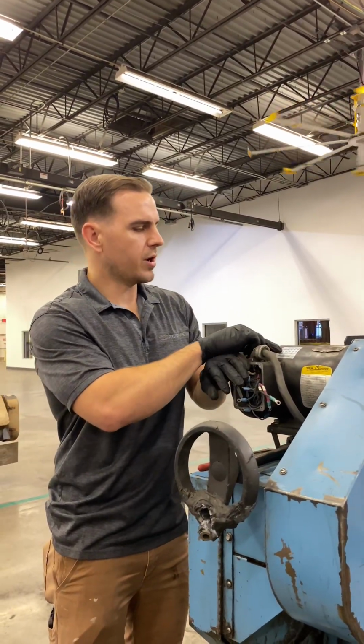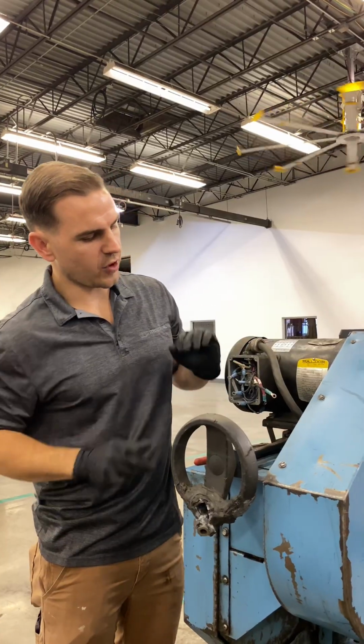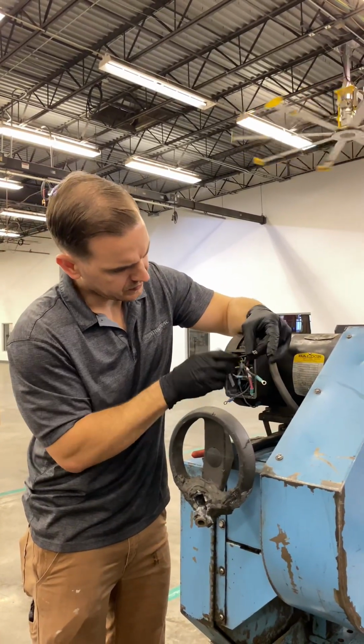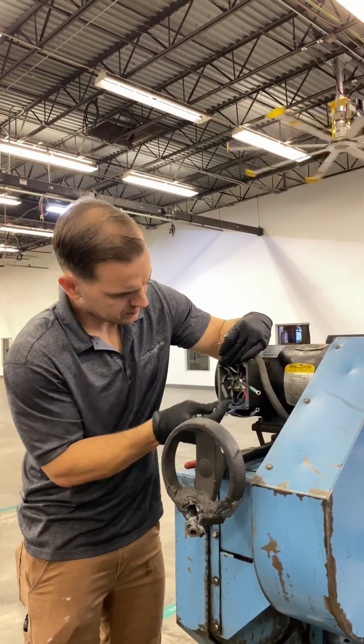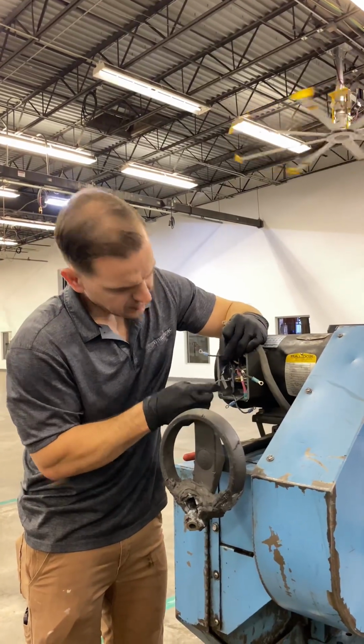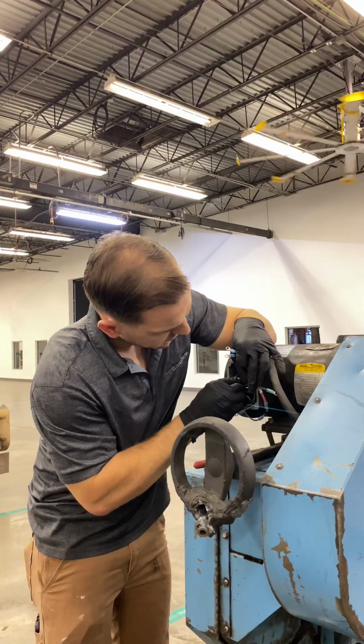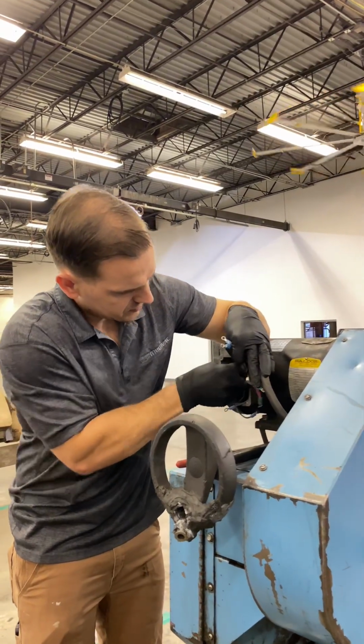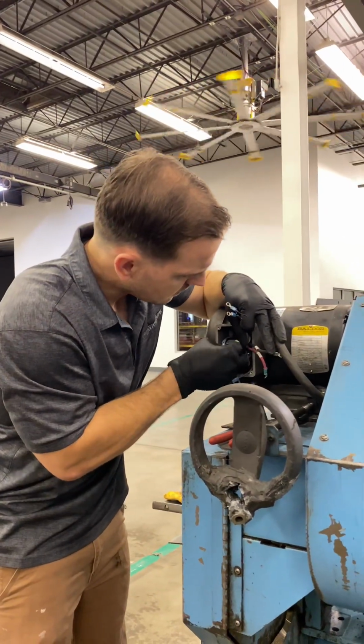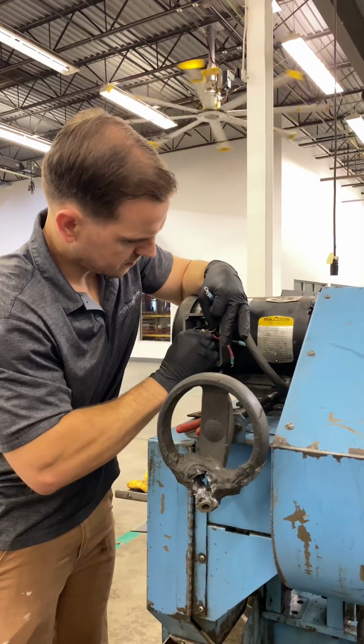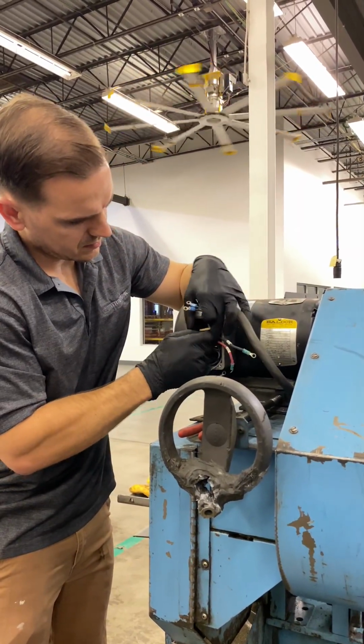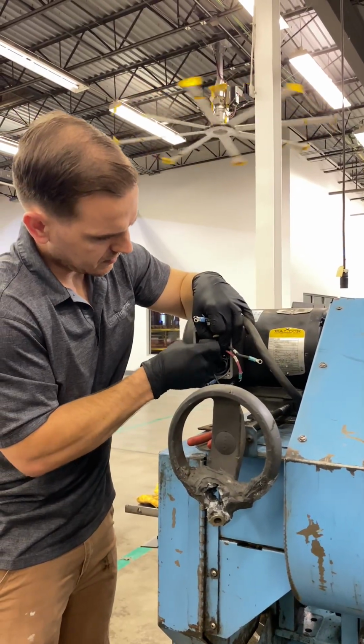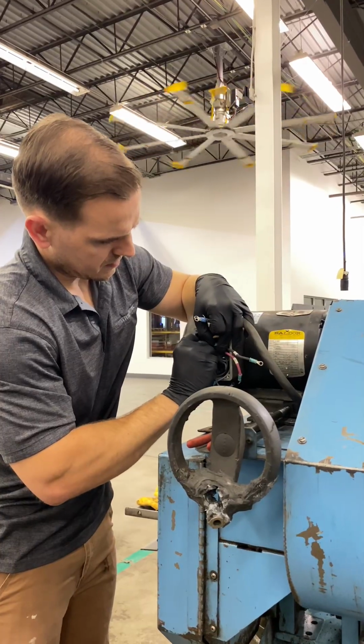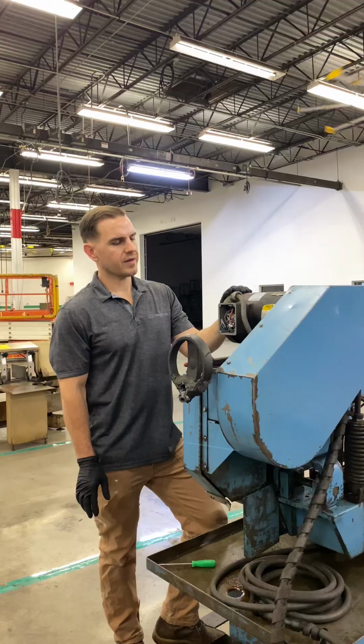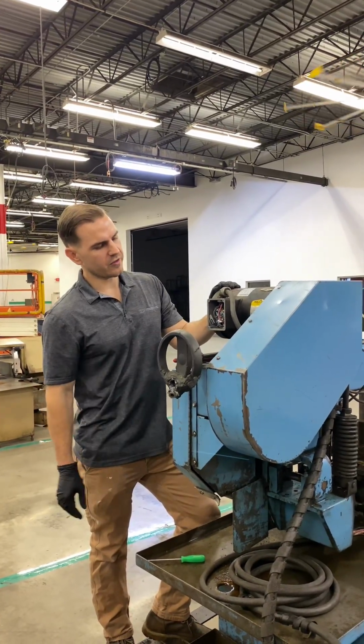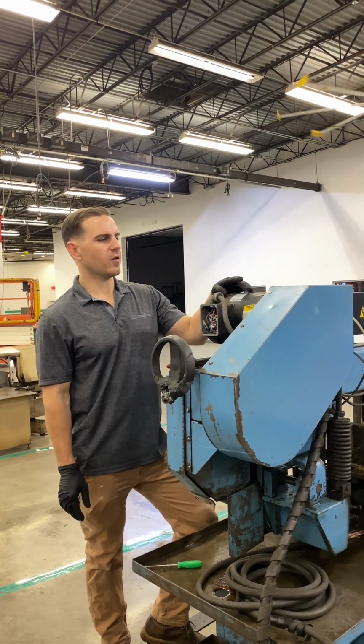And the next step for line 1 is to take wires 4 and 7 and terminate them together. Same thing. Slide these onto their own post. Take a nut. I've got all my motor terminations terminated. We're set up for 480 volts now.